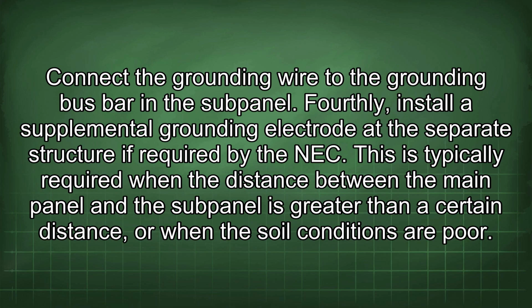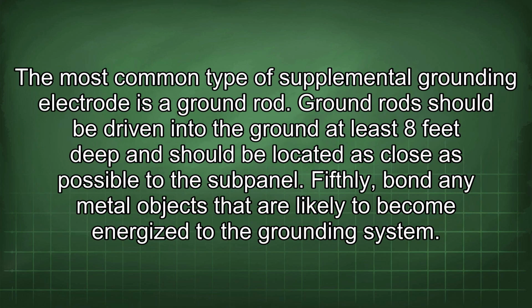Fourthly, install a supplemental grounding electrode at the separate structure if required by the NEC. This is typically required when the distance between the main panel and the subpanel is greater than a certain distance, or when the soil conditions are poor. The most common type of supplemental grounding electrode is a ground rod. Ground rods should be driven into the ground at least 8 feet deep and should be located as close as possible to the subpanel.